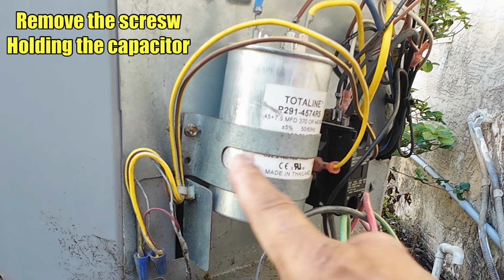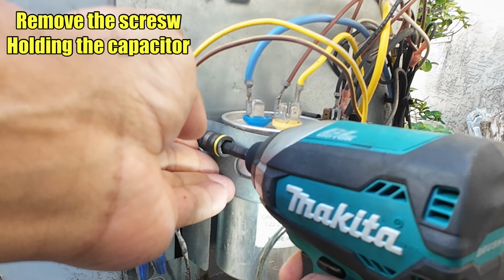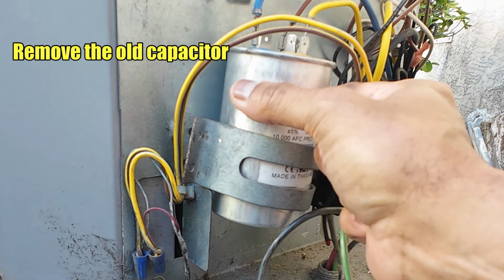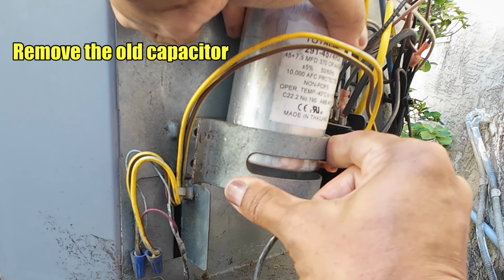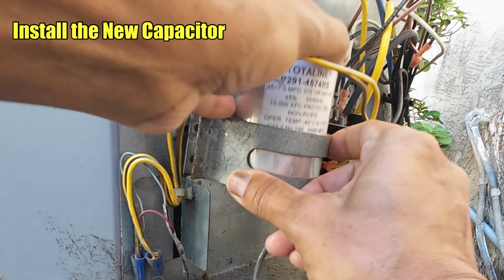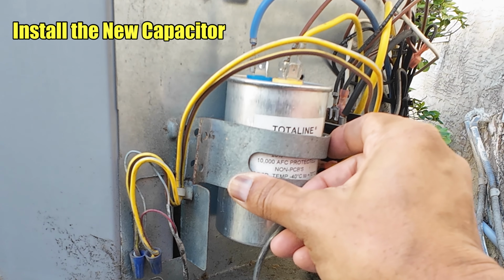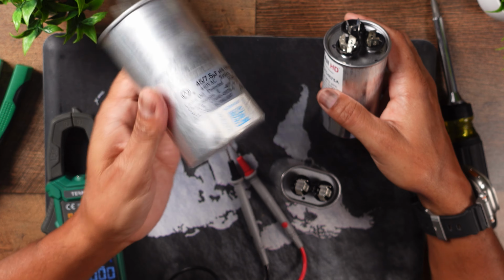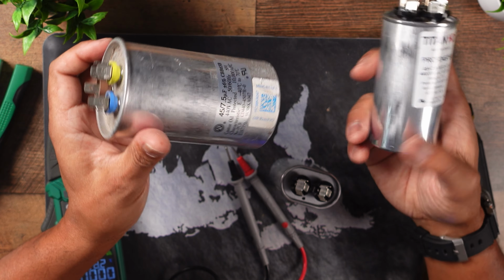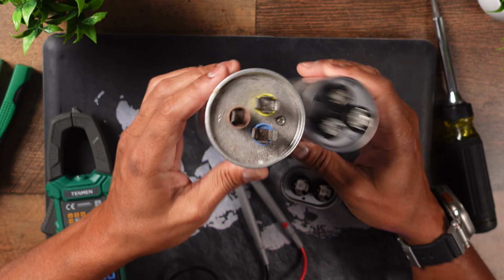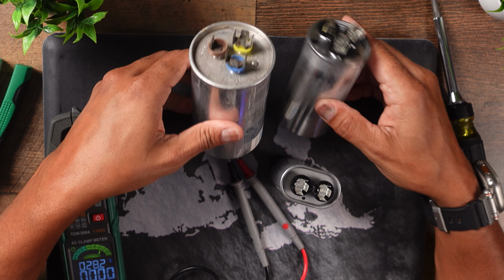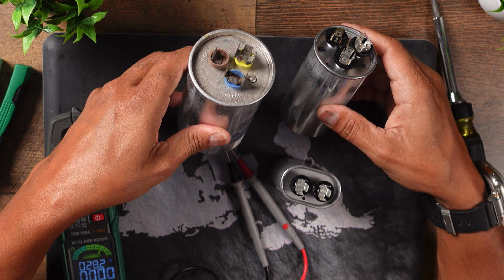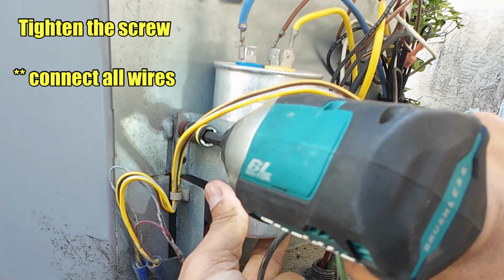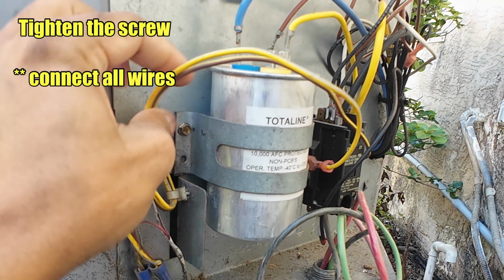Once you have the new replacement, take the old one out. You've already disconnected the wires, and it's usually held in place by a screw and a strap. Loosen the screw, slide your old capacitor out, slide the new one in. Sometimes the new ones are smaller than the old ones. In my case this is an original unit capacitor, and this one has the same specs, but you can clearly tell one is much smaller. In that scenario, you can usually adjust the strap, tighten it, and put the screw back in, and you're good to go.